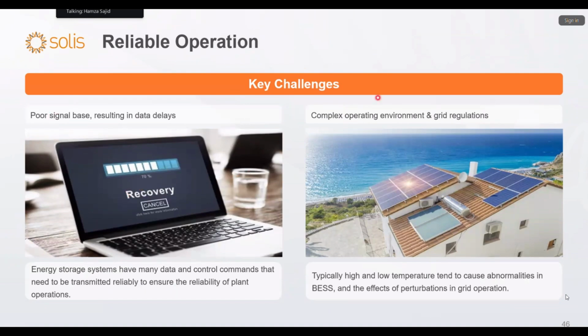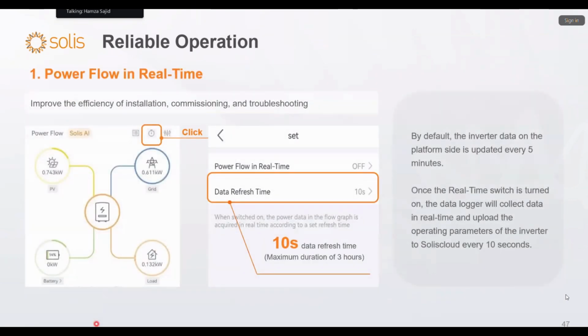Reliable operation. The key challenge for this one is the poor signal, resulting in data delays. An energy storage system has a lot of data and control commands that need to be transmitted reliably to ensure the reliability of the plant operations. There is also a complex operating environment and grid regulations. Typically, high and low temperatures tend to cause abnormalities in the BESS, and there is the effect of grid operations. So how we are going to take up these challenges is power flow in real time.